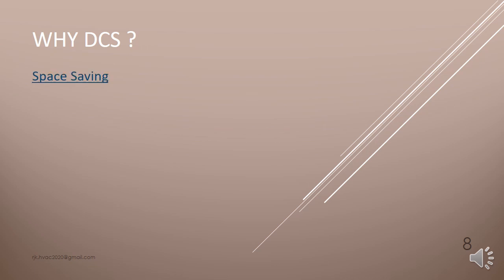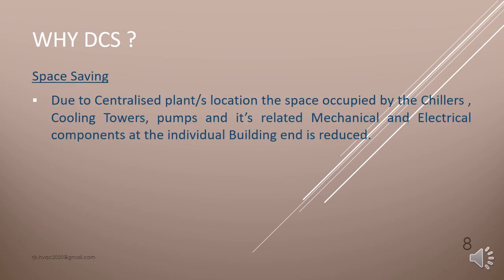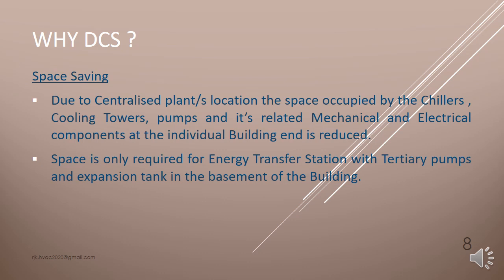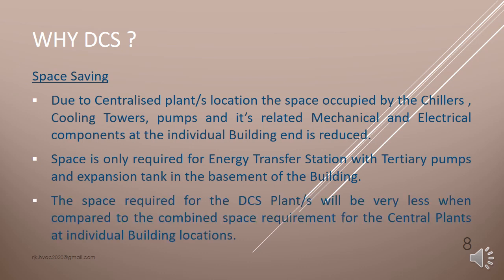Why DCS? Space saving. Due to centralized plant location, the space occupied by the chillers, cooling towers, pumps, and its related mechanical and electrical components at the individual building end is reduced. Space is only required for energy transfer stations with tertiary pumps and expansion tanks in the basement of the building. The space required for the DCS plants will be very less when compared to the combined space requirement for the central plants at individual building locations.